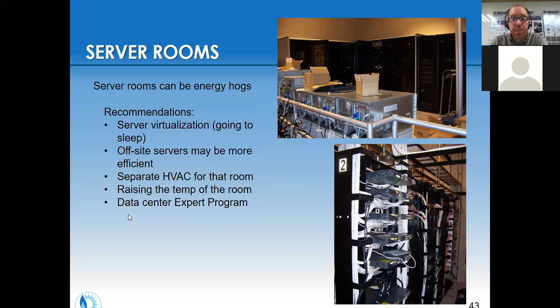All of this can really be addressed in the data center expert program that we have. Illinois Energy Now has a data center program, currently only in the ComEd service territory, with experts that can go beyond what we'd provide in a SEDAC report and do a detailed analysis on a server room for a library, looking at heat rejection, making sure cooling units are appropriate, and hot aisle/cold aisle configurations.